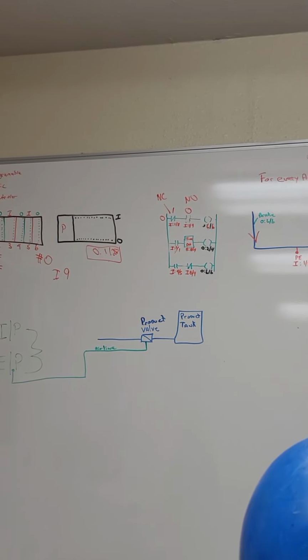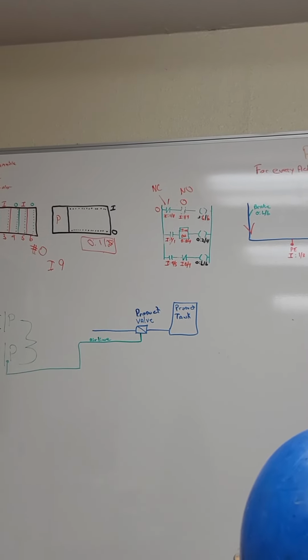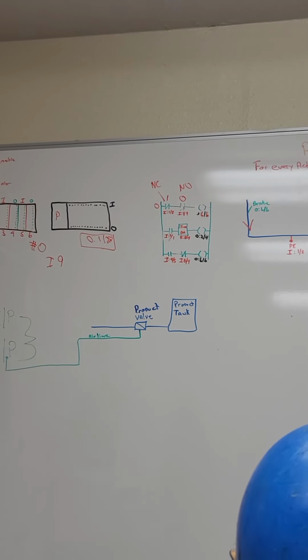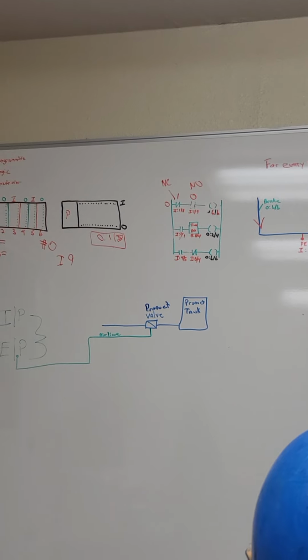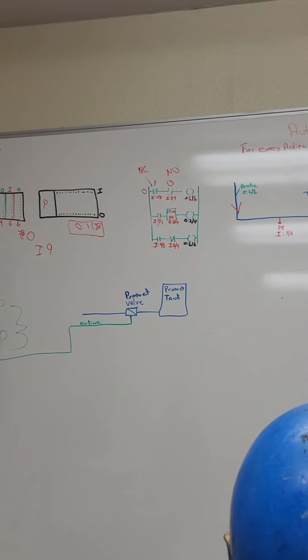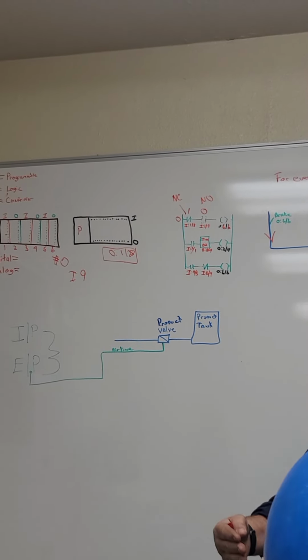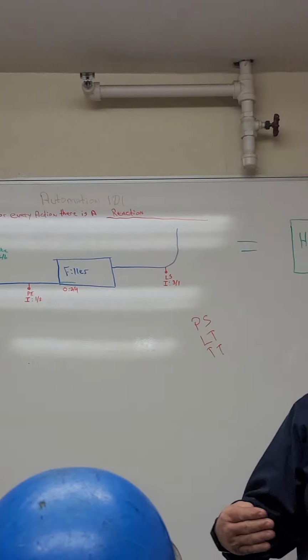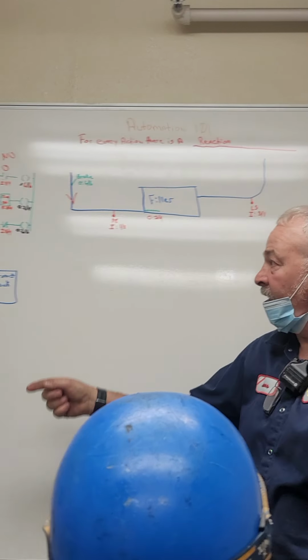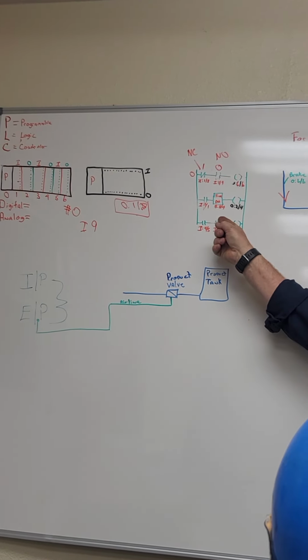Right. That's what we got on the case washers up there, you got them everywhere. All your photo eyes, most of them won't have timers on. You'll never see those. They're internal to the program. I'm just letting y'all know, if you go up and block an eye and it reacts 3 seconds later, that's why. It's not that there's anything wrong with the eye. It's because there's a timer in there.